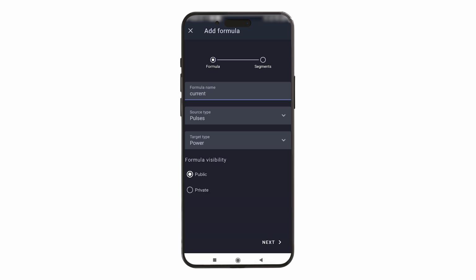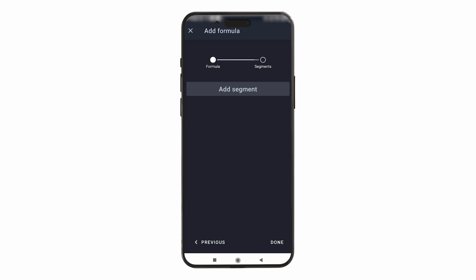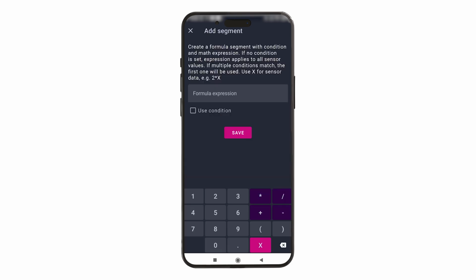A public formula allows for later editing by users with access to the formula manager, while a private formula can only be edited by the user who created it. In the second stage of creating a new formula, you need to define segments, which are logical conditions along with formulas that are meant to convert the values sent by the sensor. After pressing the Add Segment button, you should enter a new formula that will be used to convert the measurements, along with the corresponding logical condition if necessary.